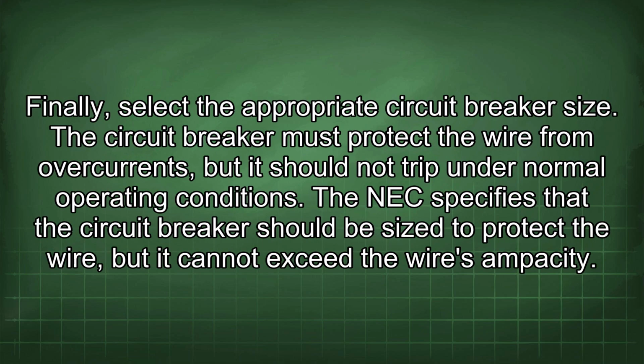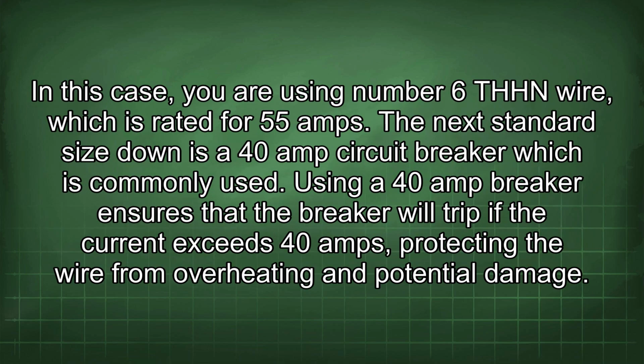Finally, select the appropriate circuit breaker size. The circuit breaker must protect the wire from overcurrents, but it should not trip under normal operating conditions. The NEC specifies that the circuit breaker should be sized to protect the wire, but it cannot exceed the wire's ampacity. In this case, you are using number 6 THHN wire, which is rated for 55 amps. The next standard size down is a 40 amp circuit breaker, which is commonly used. Using a 40 amp breaker ensures that the breaker will trip if the current exceeds 40 amps, protecting the wire from overheating and potential damage.